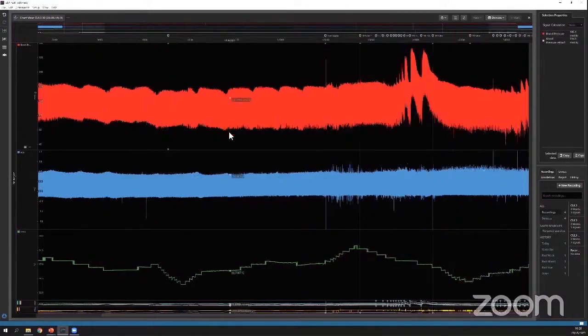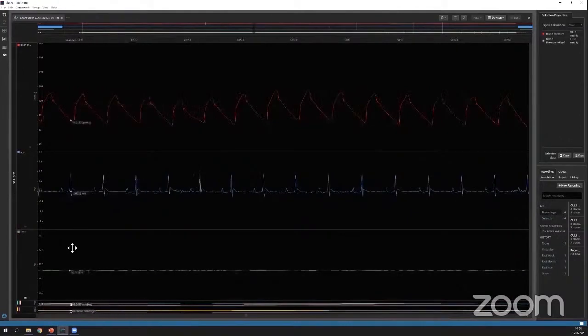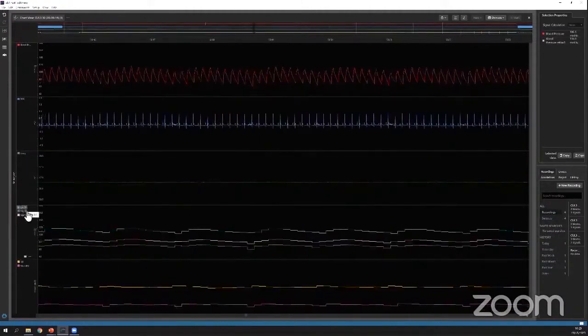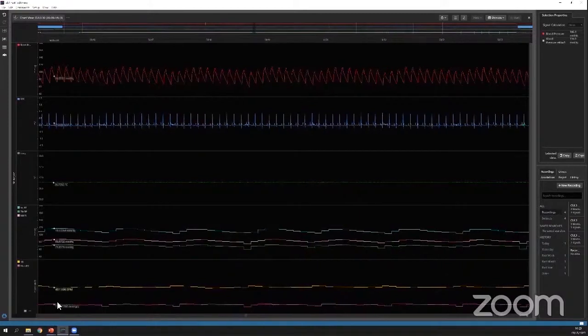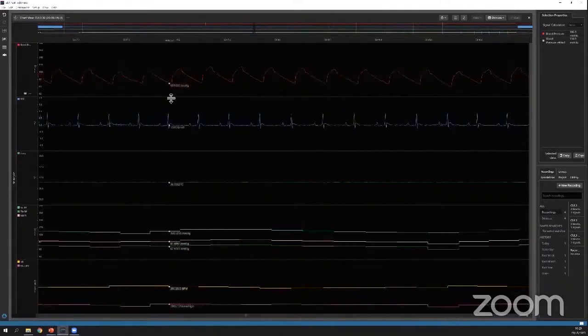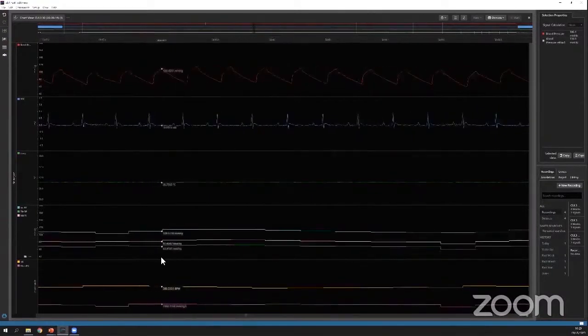We have done a stabilization period for baseline measurements, then phenylephrine administration, washout, and angiotensin II administration. You get full traces of blood pressure in red, ECG in blue, and body temperature in green. I would also have additional calculated channels: systolic, diastolic, and mean arterial pressure calculated in real time from the blood pressure data, as well as heart rate calculated from ECG R-peak to R-peak. Additionally, there's a purple line for the first derivative — the velocity of the upstroke of blood pressure — which gives an indication of inotropy, or how strongly the heart is contracting.